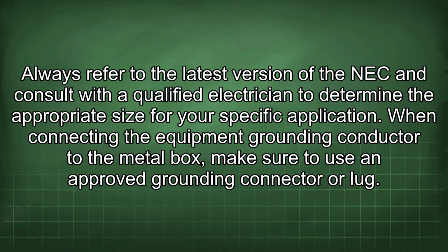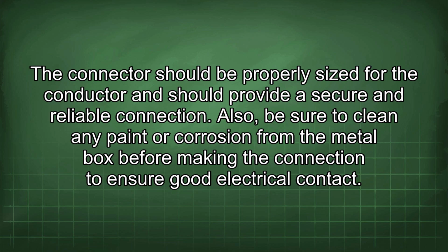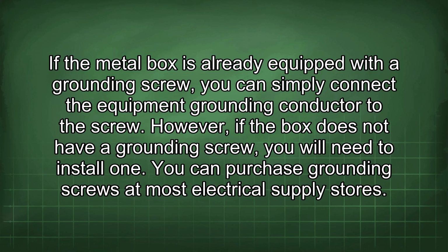for your specific application. When connecting the equipment grounding conductor to the metal box, make sure to use an approved grounding connector or lug. The connector should be properly sized for the conductor and should provide a secure and reliable connection. Also, be sure to clean any paint or corrosion from the metal box before making the connection to ensure good electrical contact. If the metal box is already equipped with a grounding screw, you can simply connect the equipment grounding conductor to the screw. However, if the box does not have a grounding screw, you will need to install one. You can purchase grounding screws at most electrical supply stores.